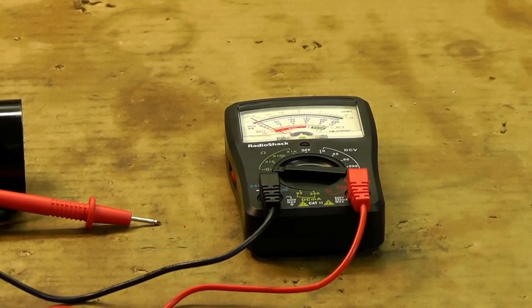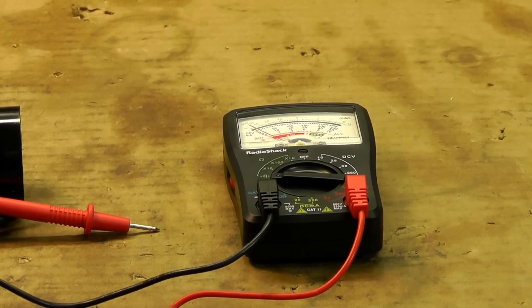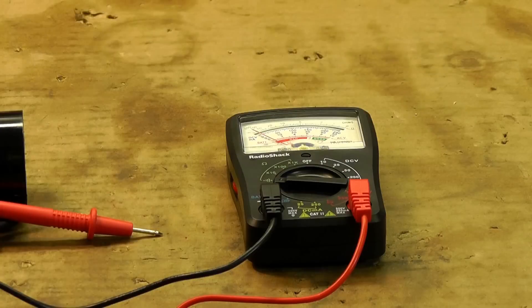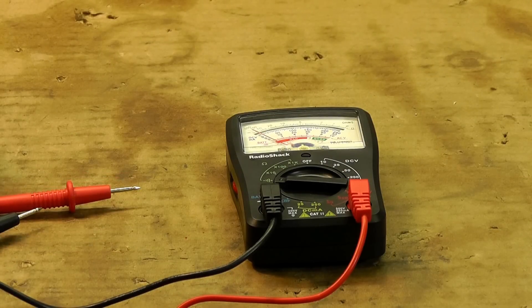You can use this as a test for any motor start or run capacitor. Typically in an air compressor, which we're concerned about here at ACPO, you'll have a defective capacitor if the motor simply doesn't start, but also if it hums when you turn it on. Sometimes it will simply hum, make a noise like that, or it won't stay running. If that is the case, then you probably have a defective capacitor.